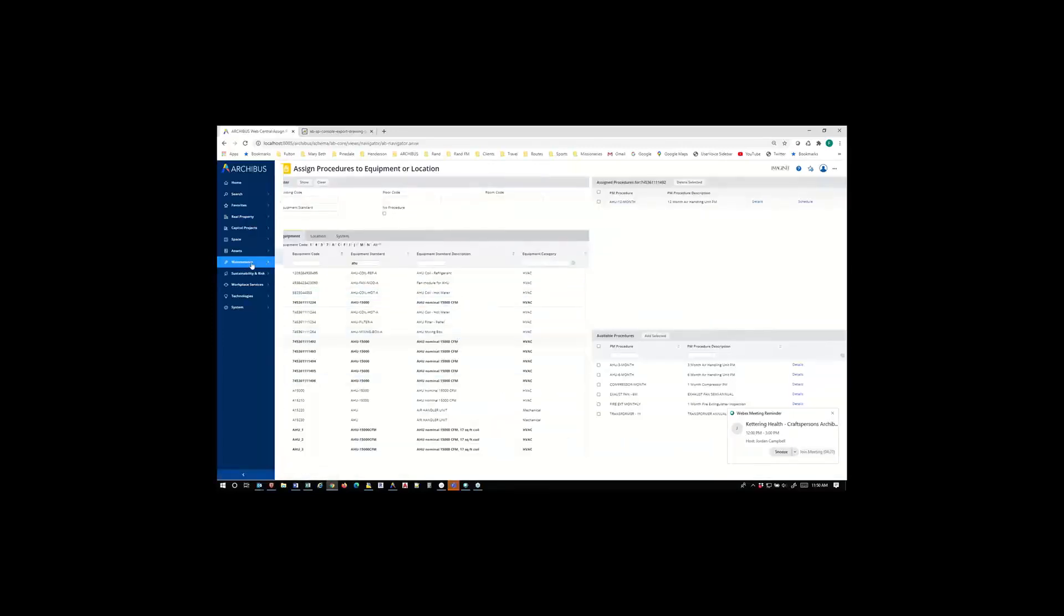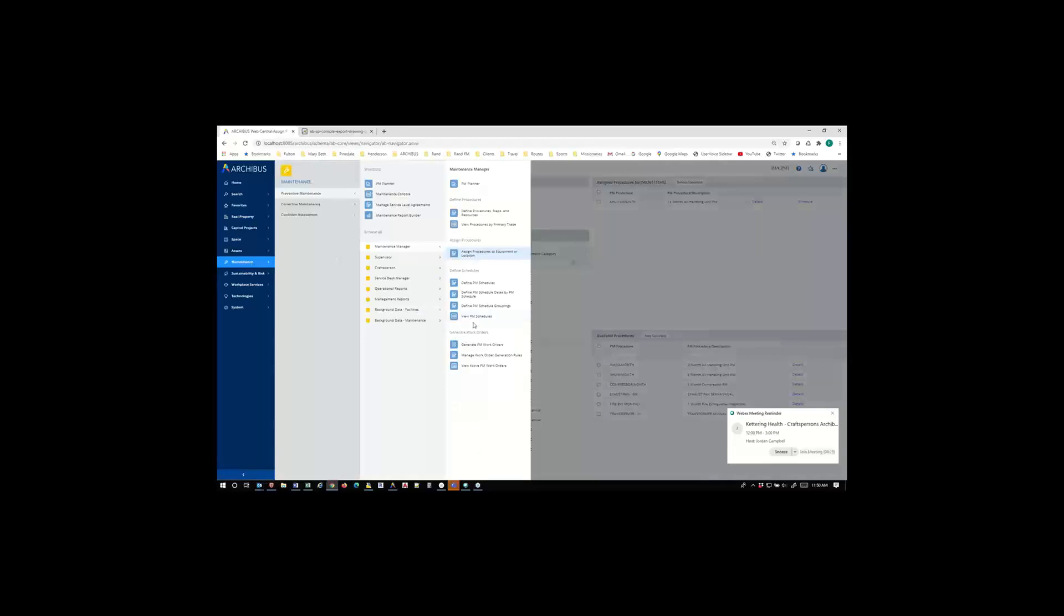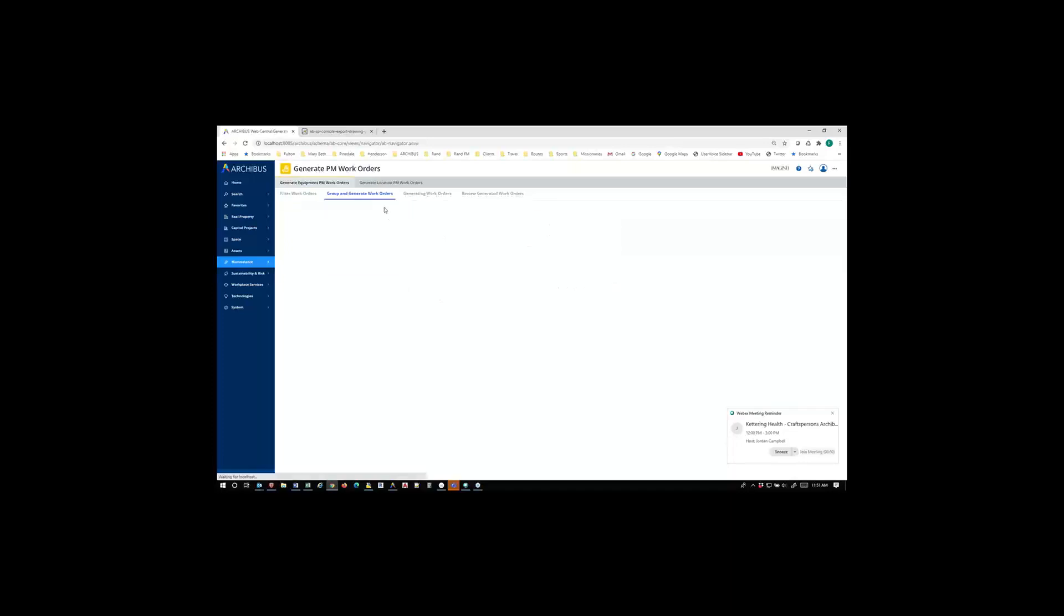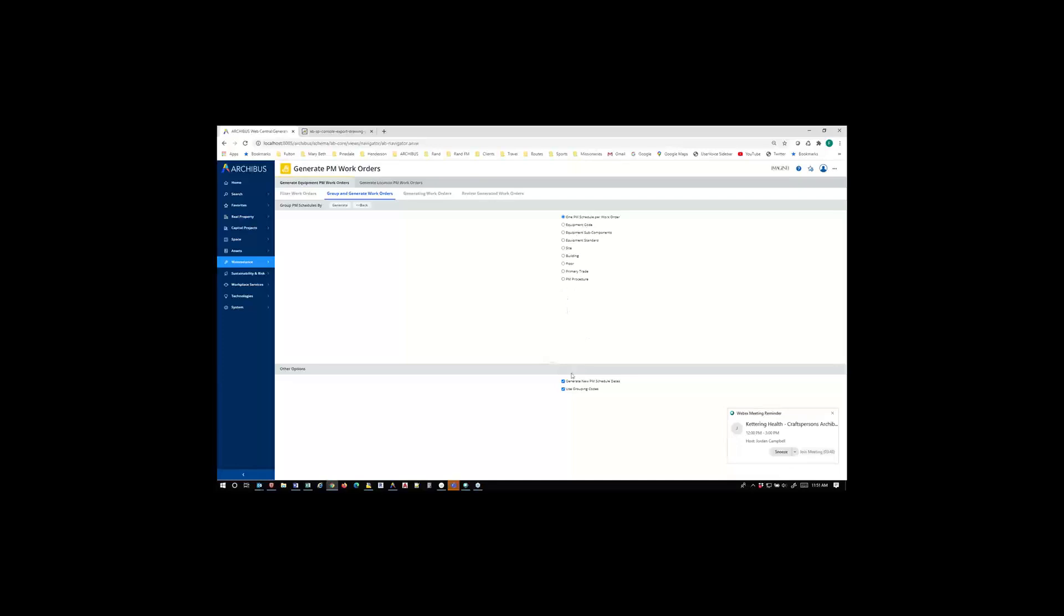So that kind of depends on whether you need to comply. If you have compliance issues and you need to prove that you have one coming out every month, then you need to do fixed. If you're just trying to be efficient, then floating might be a better choice. So once you've scheduled those, then the next part of the process is to generate them. The way you generate them is to come here. You can sort them if you choose. You have a day range. So if we were going to do this for this week, or from now going forward, you can't generate backwards, although you can catch up if you miss some. So we have this. So then we go to the next section. And again, we can have one PM schedule per work order, or we can sort it by equipment or by other things here, and then we generate.